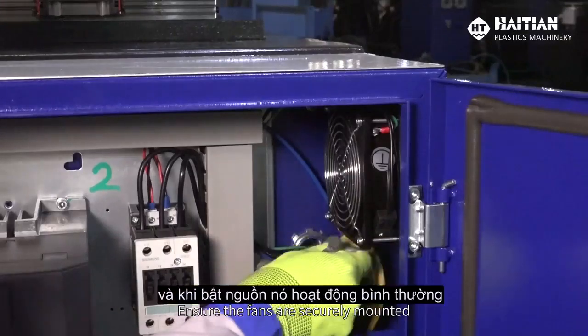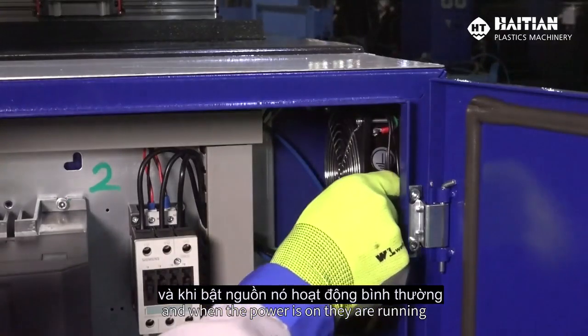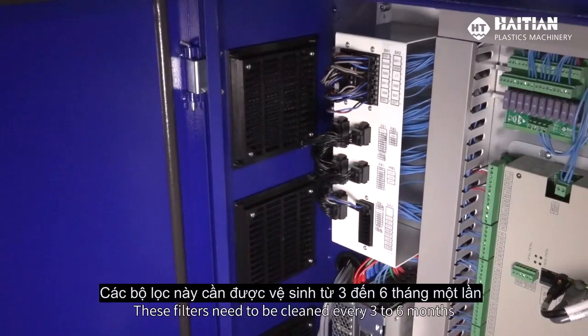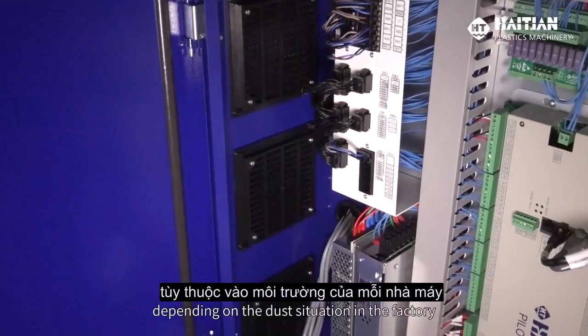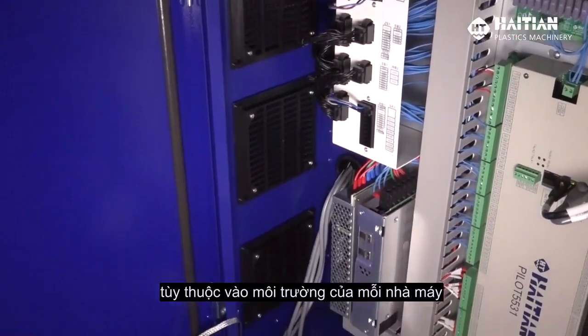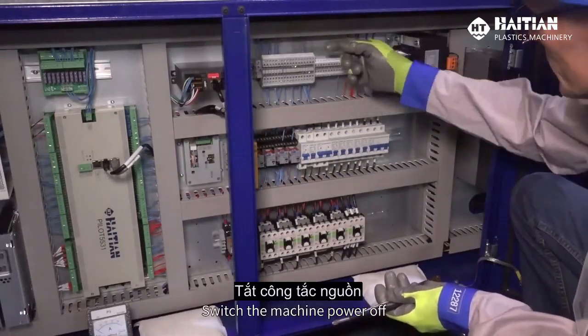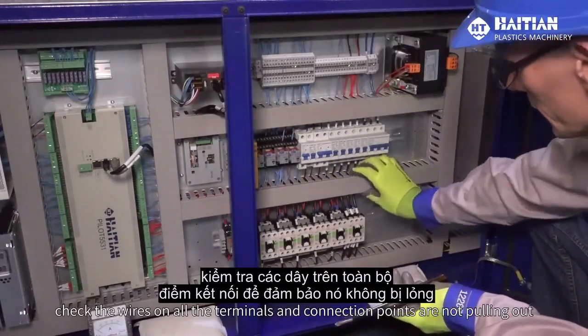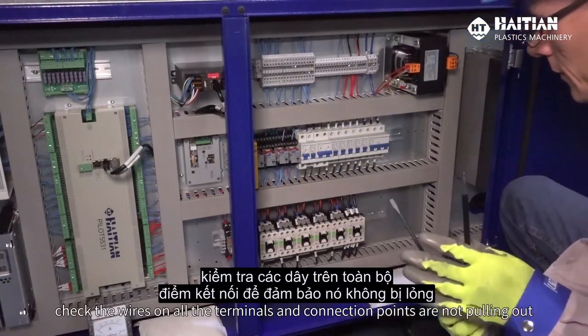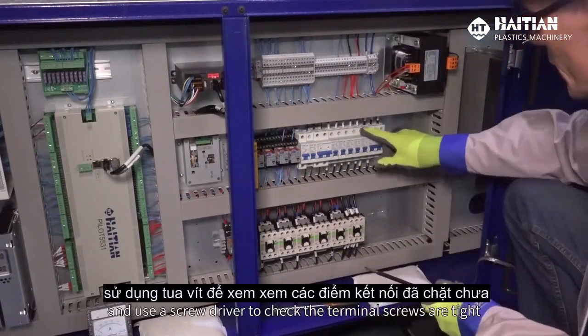Ensure the fans are securely mounted and when the power is on they are running. These filters need to be cleaned every 3 to 6 months depending on the dust situation in the factory. Switch the machine power off. Check the wires on the terminals and connection points are not pulling out, and use a screwdriver to check that the terminal screws are tight.